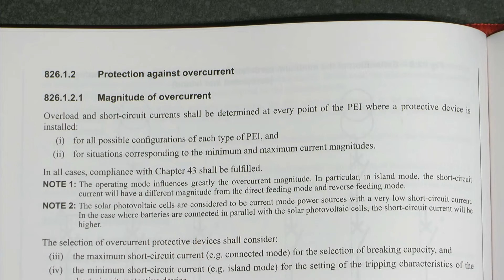In fact, so low that it may not actually cause circuit breakers to trip. So you may need to think about different types of protective device, or different ratings of them, and again putting them in different places. It's absolutely essential to consider all the different operating modes, where the electricity is coming from and going to, making sure your protective devices are in appropriate locations and will actually work if faults occur in any of these operating modes.